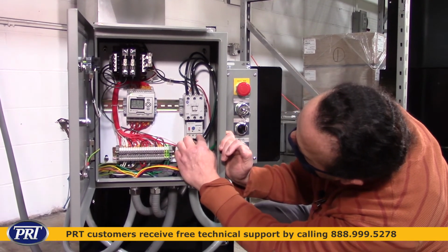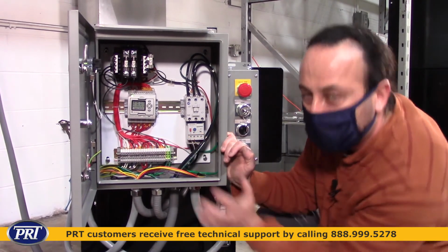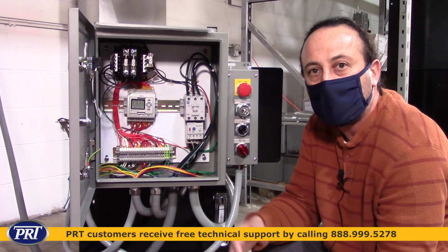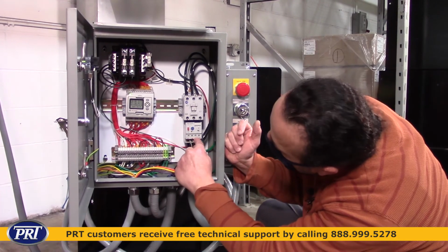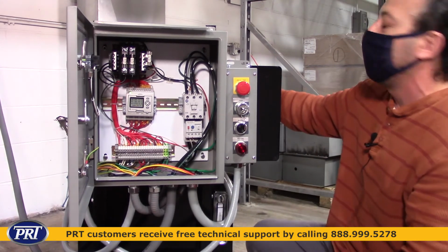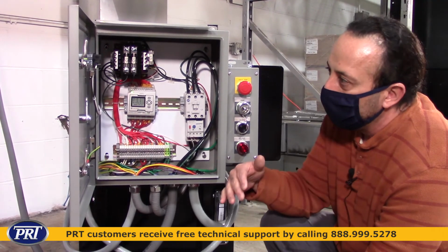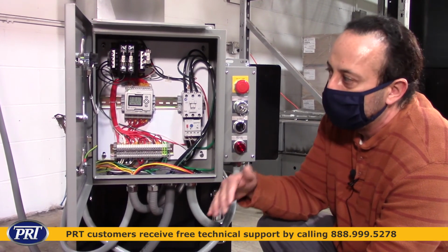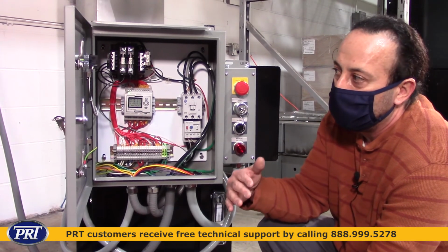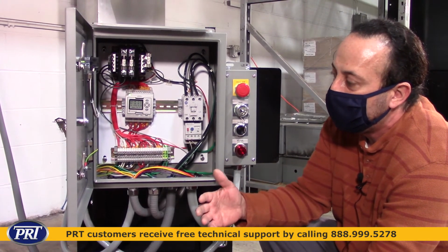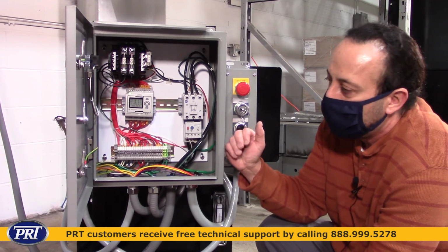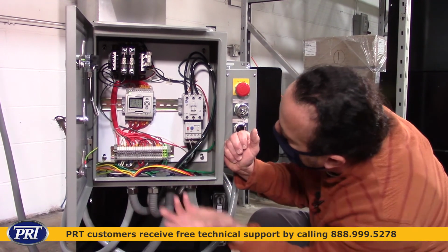There's a little dial, and this one here is rated from 9 to 45 amps, which is plenty for a 10 horsepower motor. And where you would get that number from is over here on the motor plate, where it says your amperage versus your voltage. In this case, voltage is 208, and the amperage on there says about 27 amps, so we dial this into about 27 amps.